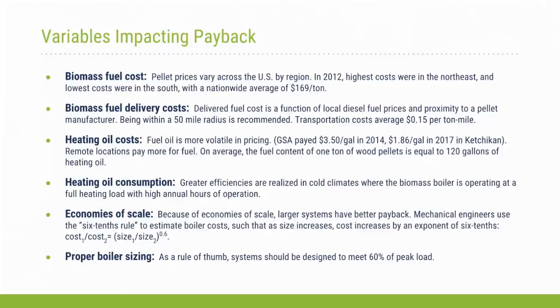Economy of scale—again, the bigger the project, the more economical it is. Proper boiler sizing is also key. There's a rule of thumb, and I've heard different versions, to size it at 60% of peak load—some say 75%, some say 50%. If load data is available for a project, it makes more sense to run that data and optimize the sizing, because an oversized boiler wastes capital, and an undersized one means burning too much of the alternative fuel.